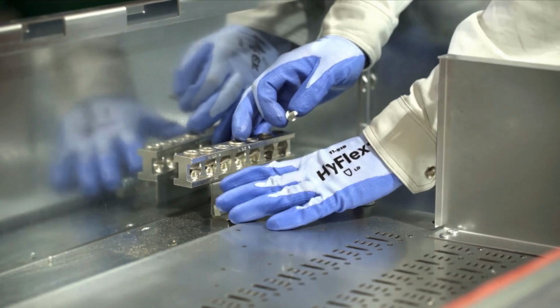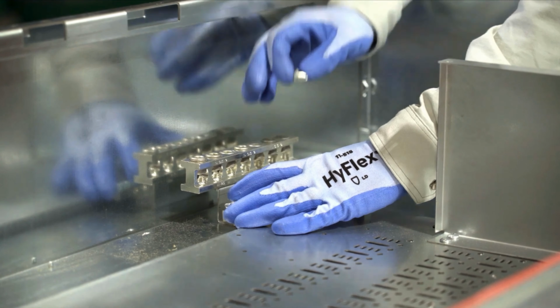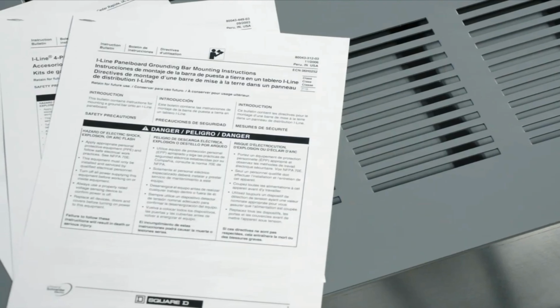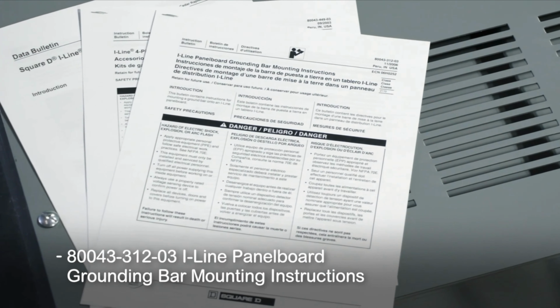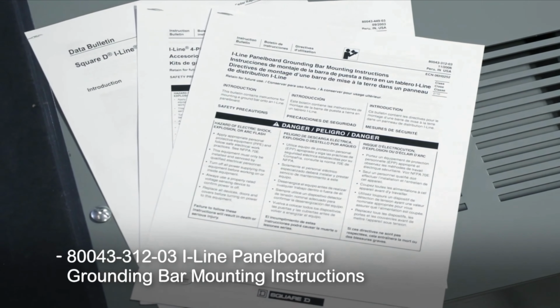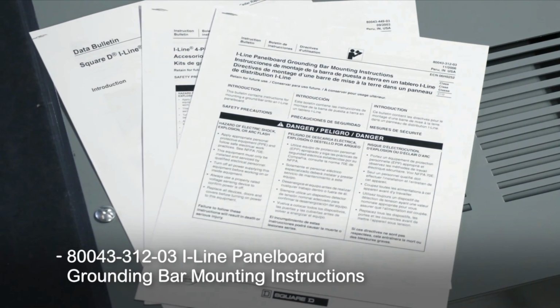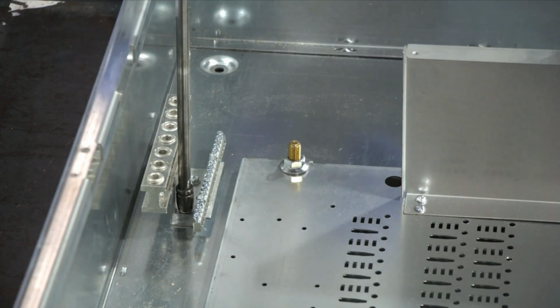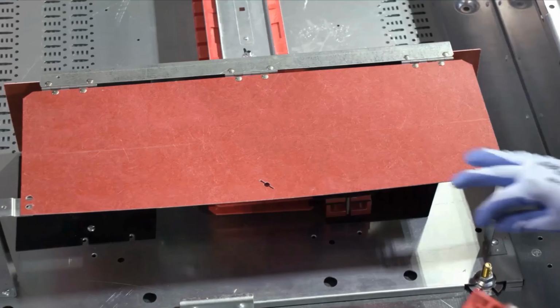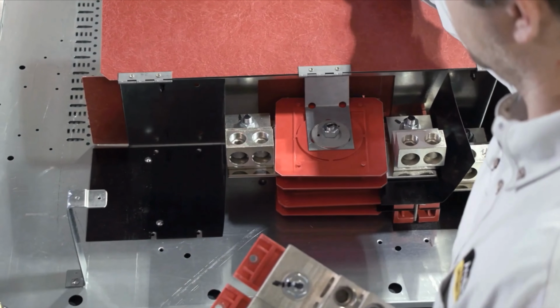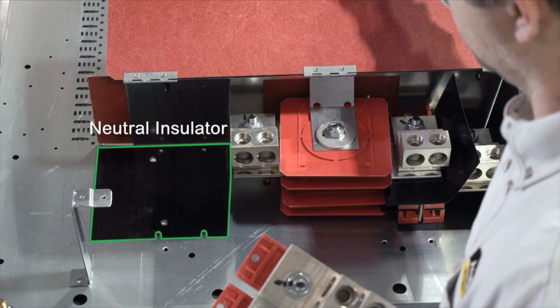The included ground bar can be placed in multiple locations in the I-line power distribution panel board. Refer to 80043-31203 I-line panel board grounding bar mounting instructions for details. Place and secure as shown. Next, be sure the neutral insulator is already installed in the equipment, as it is required before proceeding. If not installed, electric shock, explosion, or arc flash can occur. If the neutral insulator isn't already installed, contact Schneider Electric's Customer Care Center for assistance.